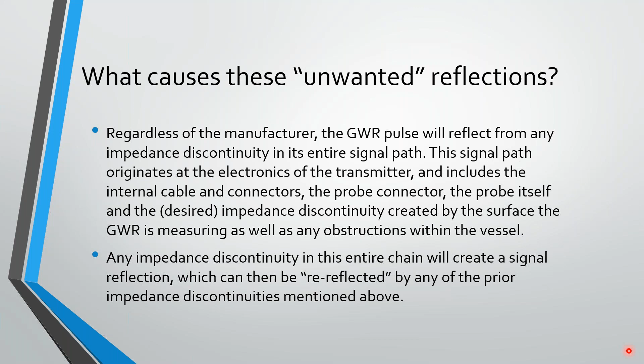Majority of the problems when it comes to radar level devices is improper installation, not following the manufacturer's guidelines, not selecting the right probe. Right there, that probably covers about 98% of your problems. Sometimes if we simply can't avoid agitators, or if there's just way too much turbulence within the vessel, we may need to install a stilling well and have the device installed within that stilling well.